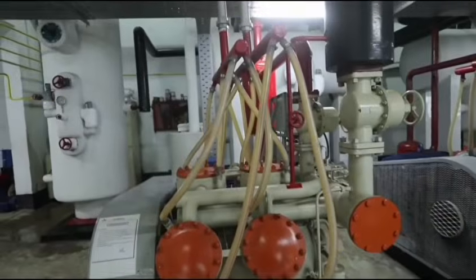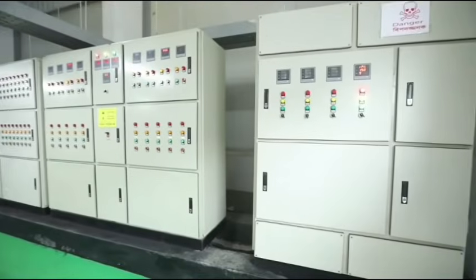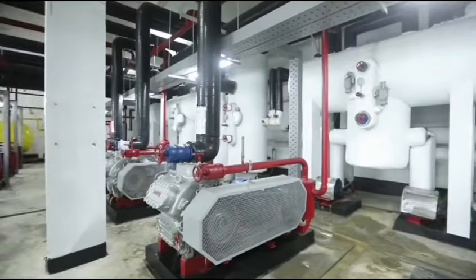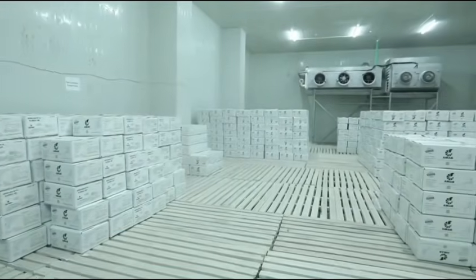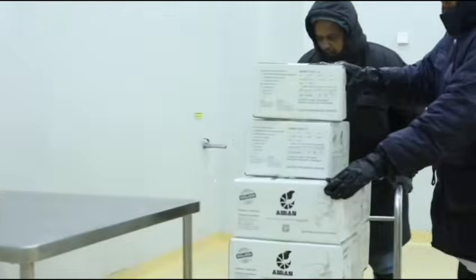These are all due to slow opening doors, an ineffective defrosting system, etc. Low evaporation temperature ultimately, and multiple defrosting cycles, heavy load on the refrigeration system, etc. Due to this melting ice and formation of ice, barcodes we cannot detect properly and the packaging material also gets damaged. So a lot of disadvantages are there. Finally, it leads to non-productive workflow.